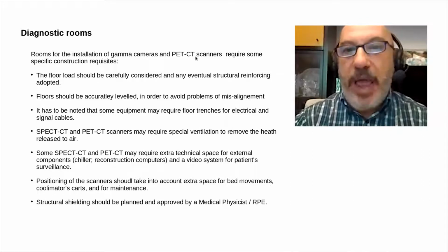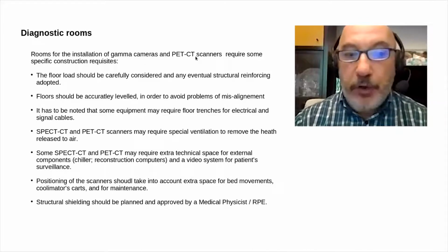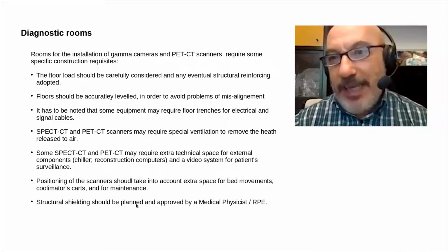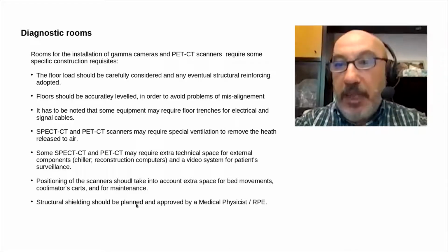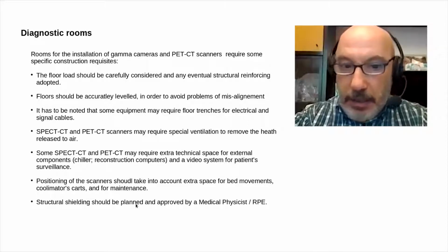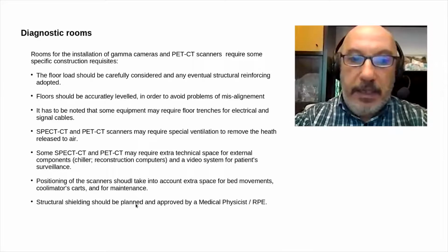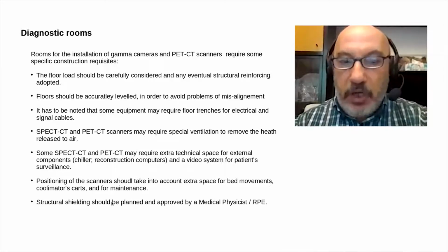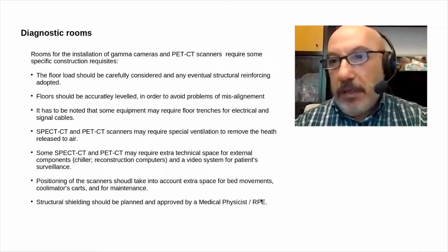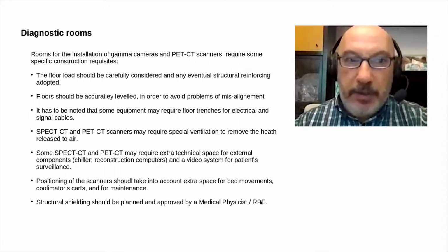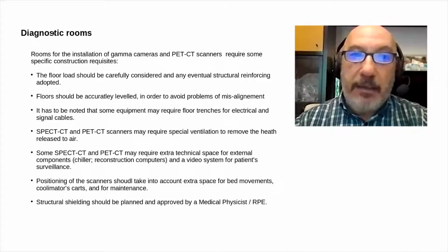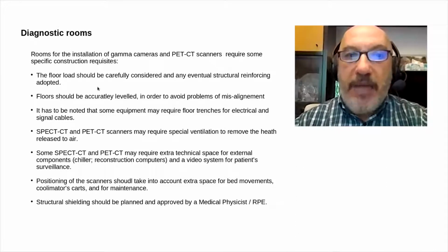The diagnostic room has a lot of requisites. First of all, the last in my bullet list is structural shielding. I will not deal with the detail of structural shielding in this presentation because this would require another full presentation. It is the case in this occasion simply to say that structural shielding should be planned and approved by a qualified medical physicist or radiological protection expert as appropriate and depending on your national regulation.